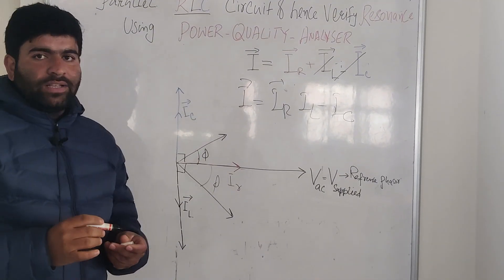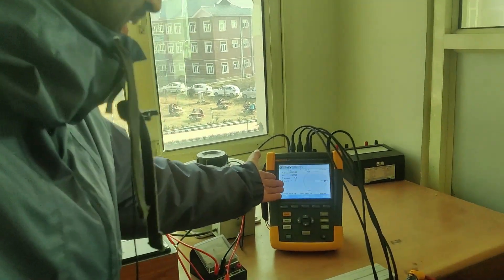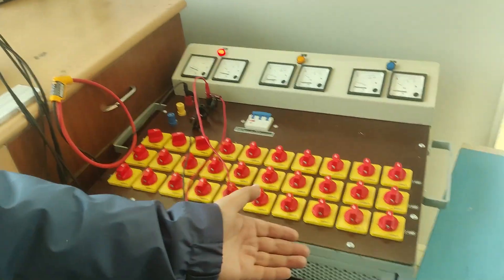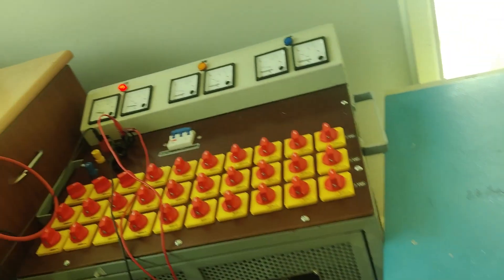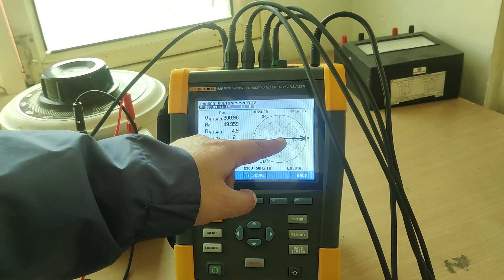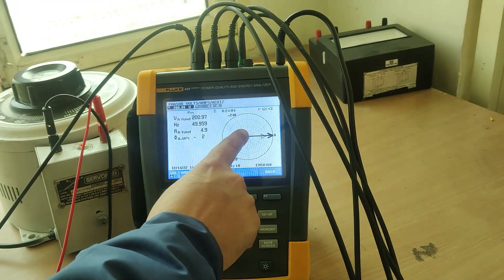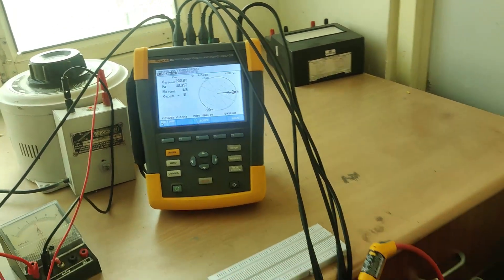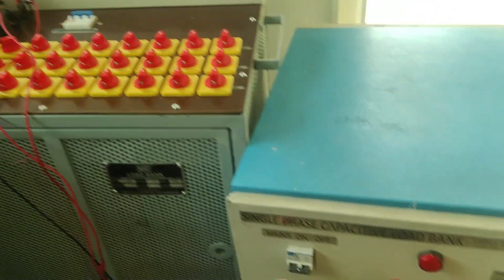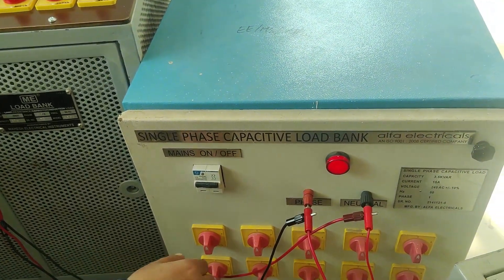This is our experimental setup. You can see the power quality analyzer, the watt meter, the resistor load bank, the capacitor load bank, and the inductive load bank. We have connected only the resistive load bank first. As you can see on the display, the voltage and current are in phase — the larger line is the voltage and the shorter one is the current. Now I will connect and switch on the capacitive load.